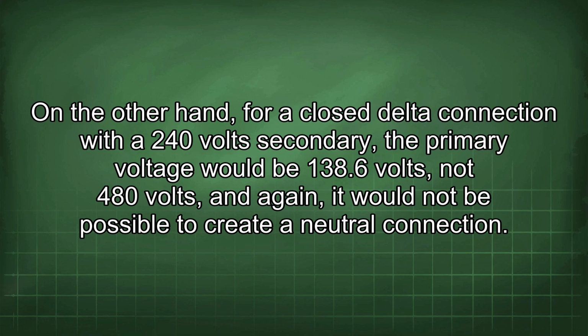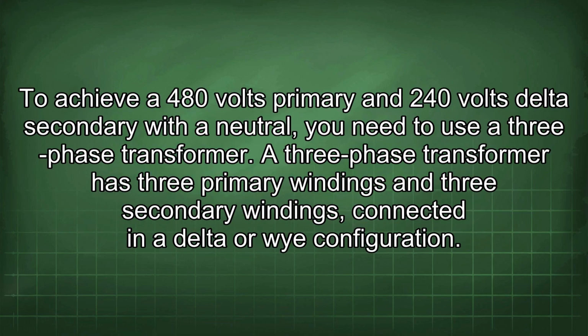On the other hand, for a closed delta connection with a 240 volt secondary, the primary voltage would be 138.6 volts, not 480 volts, and again, it would not be possible to create a neutral connection. To achieve a 480 volts primary and 240 volts delta secondary with a neutral, you need to use a three-phase transformer. A three-phase transformer has three primary windings and three secondary windings connected in a delta or Y configuration.